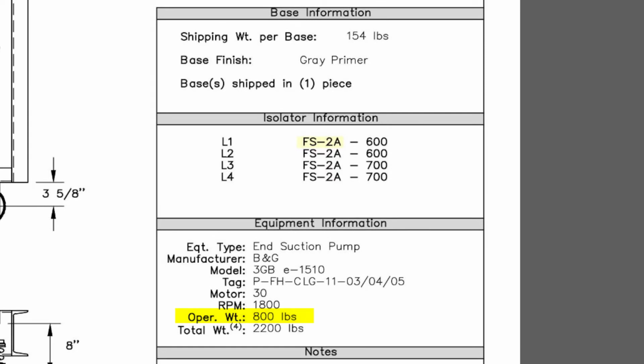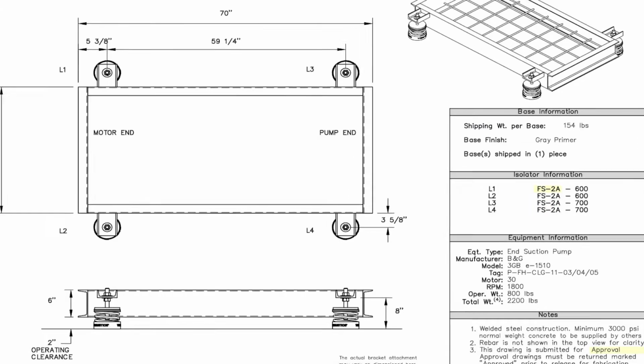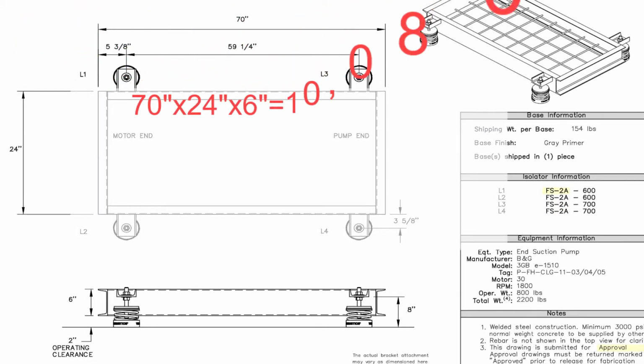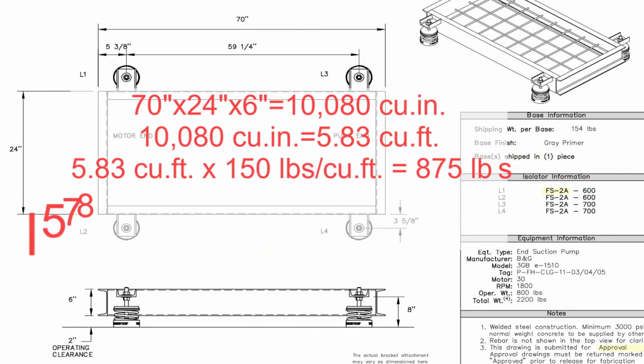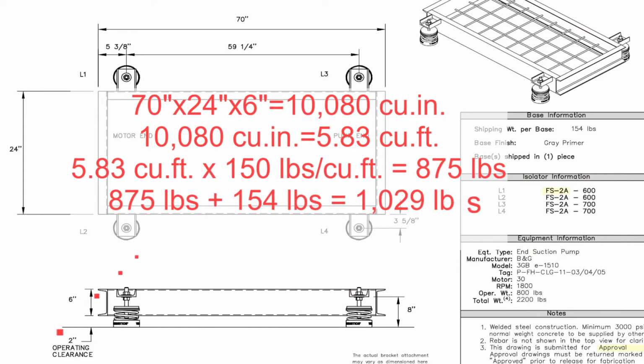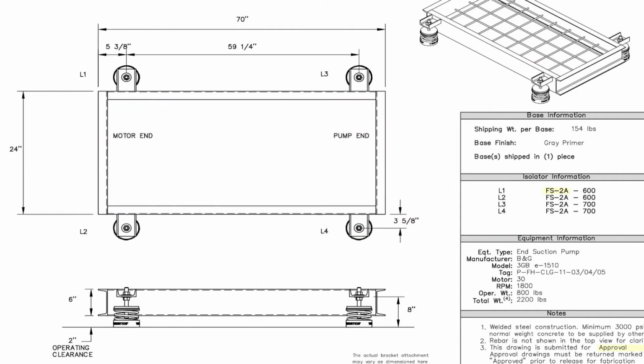These pumps weigh 800 pounds each. These bases weigh 154 pounds each without concrete in them. A quick rule of thumb to use for determining the weight of the concrete is to determine the volume of concrete and multiply it by about 150 pounds per cubic foot. Add the base weight to the concrete, and for this one, you'll get just over 1,000 pounds each, which is more than the 800-pound pump sitting on it.